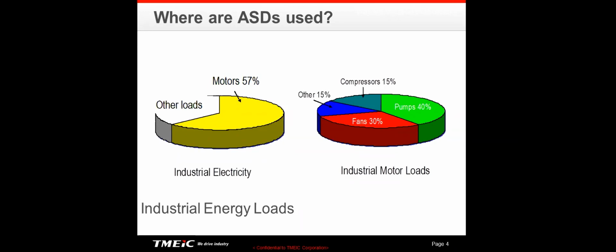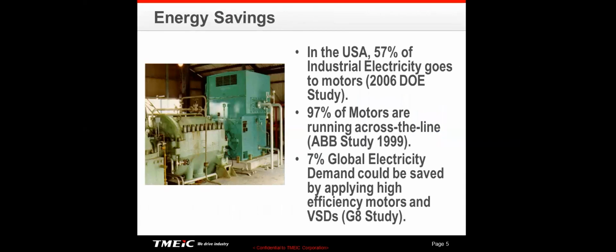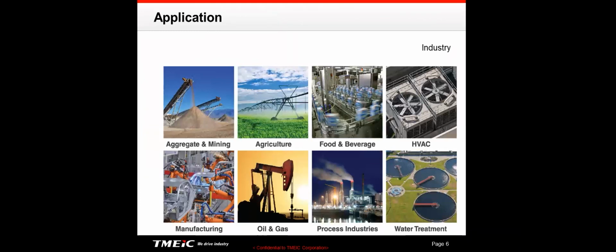As you can see, with industrial electricity, motors use about 57% of all the electricity used in industrial plants. If we look at industrial motor loads, 15% of those on drives are compressors, 40% on pumps, 30% on fans. And so you can see why that's a pretty important application for variable frequency drives. 97% of motors in the United States are running across the line. That's an ABB study. And if we were to use variable frequency drives in places where they could save energy, we could save approximately 7% of the global electricity demand. So that's a pretty significant thing.